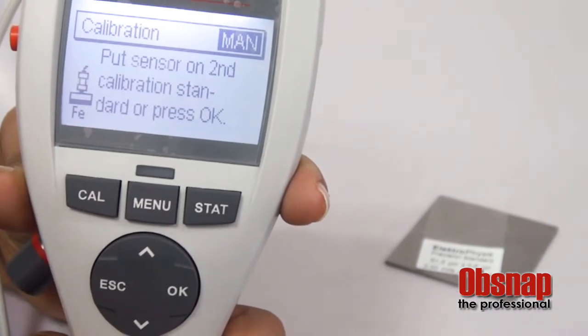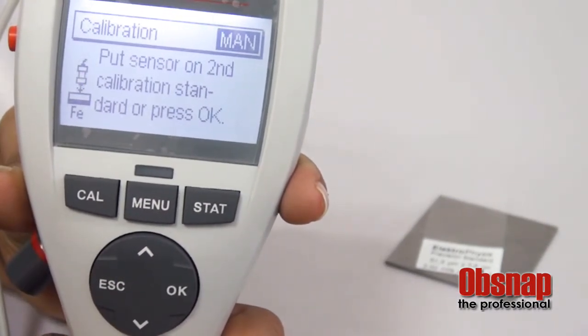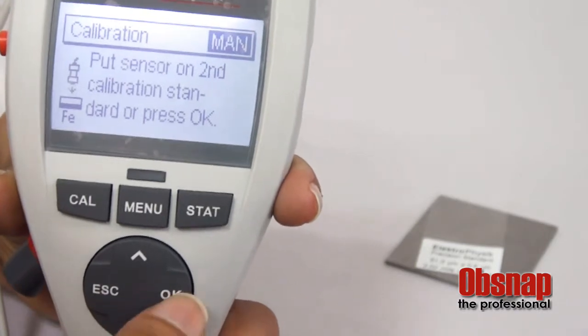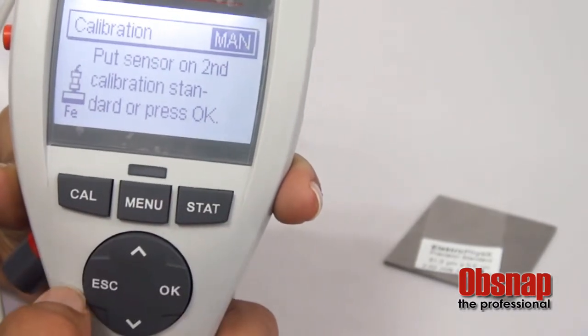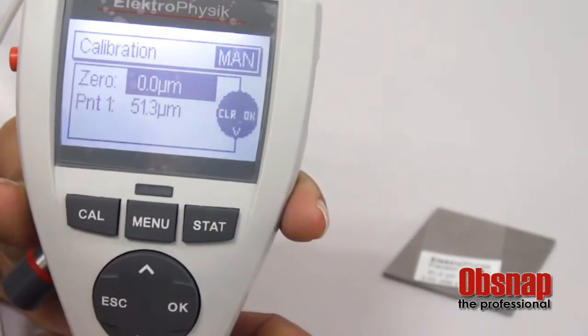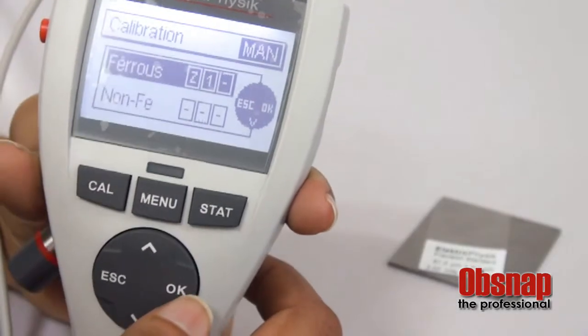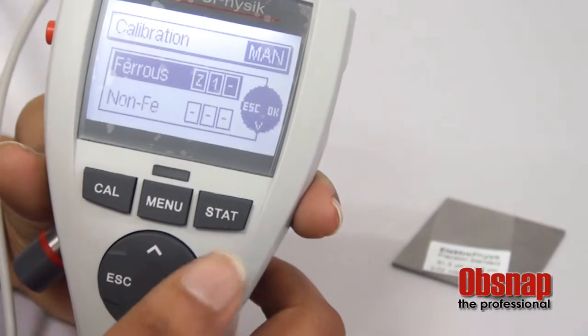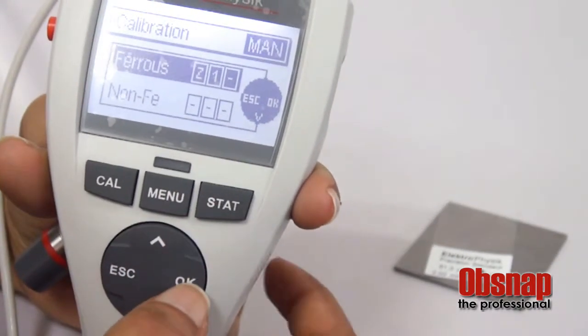Then this is the second calibration standard. If you want to ignore the second calibration standard, you just click OK button. So this is what we call 1 point calibration.